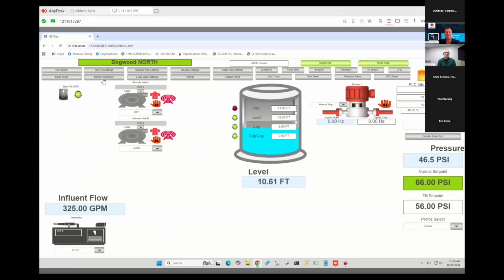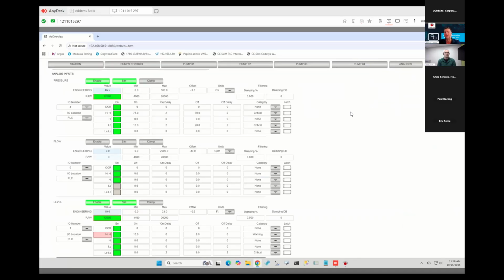So once we have our I/O mapped, then we go into our booster controller. Here's the main things the booster controller is looking at. So this is where we're maintaining pressure, maintaining flow, or maintaining a level from those booster pumps. Here we can now come in and set all of our alarming, and we can change the alarms here too to know, is it an info, a warning, or a critical alarm? And is it latched?